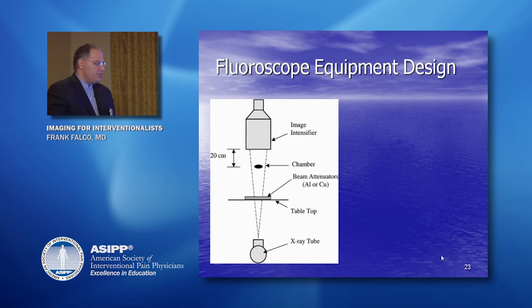The fluoroscope equipment design is that at the bottom here, we have our X-ray tube. The cathode and anode are here. It creates the electrical energy. It hits the image intensifier that is coated with phosphorus, and from that, light is emitted, and that light is then transferred to an electrical signal that goes to the processor, and we create an image.